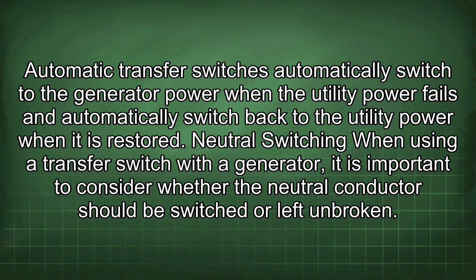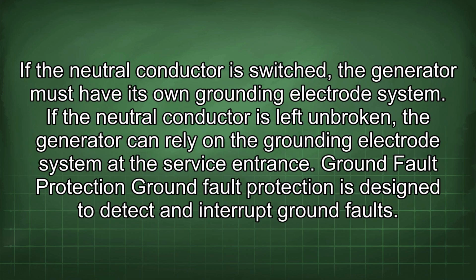Neutral switching. When using a transfer switch with the generator, it is important to consider whether the neutral conductor should be switched or left unbroken. If the neutral conductor is switched, the generator must have its own grounding electrode system.